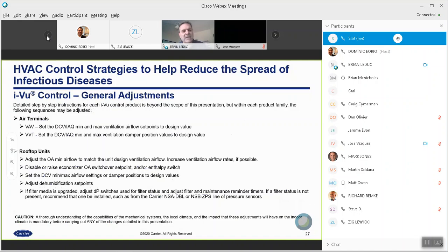Okay, I did say we were going to talk about i-Vu, and these are some of the adjustments that we think you could do if you're asked to try to comply with this guidance. Again, you'll see the ASHRAE paper, the ASHRAE documentation, and the Taylor paper. They recommend not using DCV in its traditional way, where you're attempting to allow lower than design ventilation rates. Really, the ASHRAE doesn't explain why.